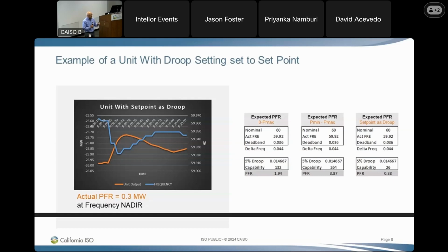Why are people putting a set point? Because when units are sitting at 0, they don't want to provide frequency response. I understand that you may not want to be providing frequency response in the middle of the night. Change your controller logic to say, if I'm at 0, then 0. Don't put your droop on set point to accomplish that, because you're shortchanging the interconnection. This unit has the worst of all the scenarios established for its droop setting.